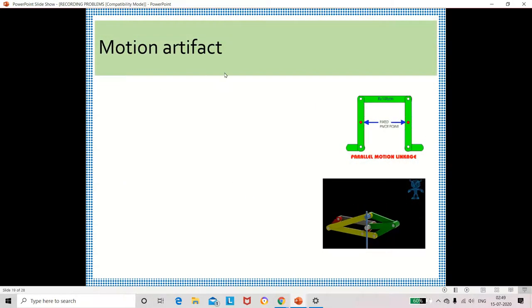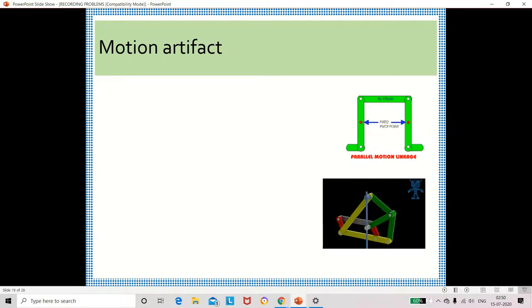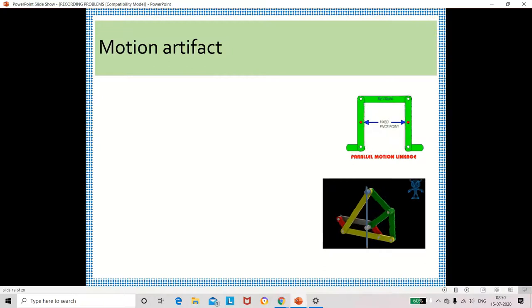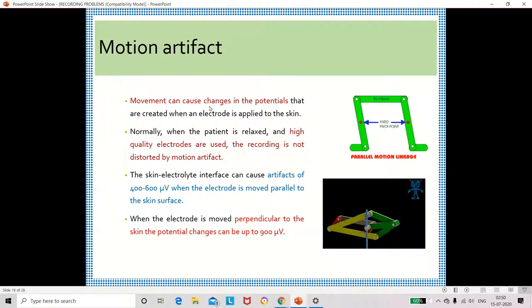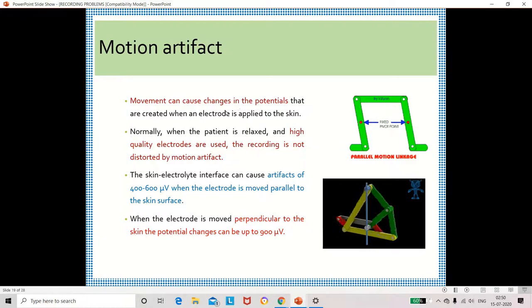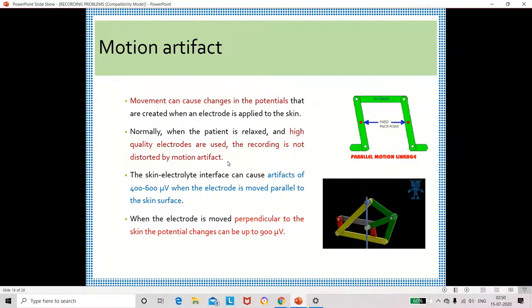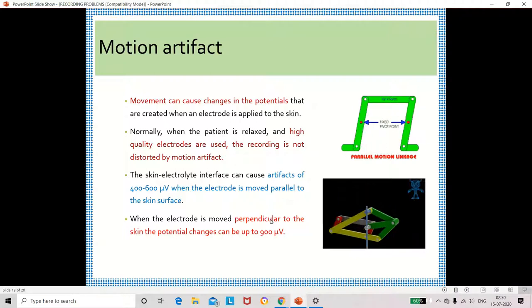The next noise source is motion artifact, which is a movement error. Sometimes we may move the electrode while fixing it on the patient, or the electrode may be shifted — either in a perpendicular manner or a parallel manner. Due to the movement of the electrode or the patient, there will be changes in potential that create noise. High quality electrodes should be used to avoid this motion artifact.